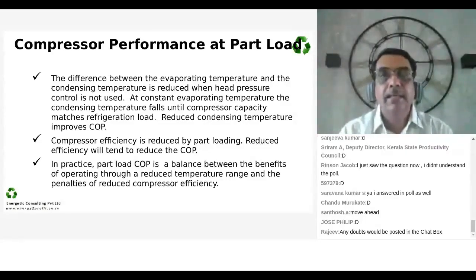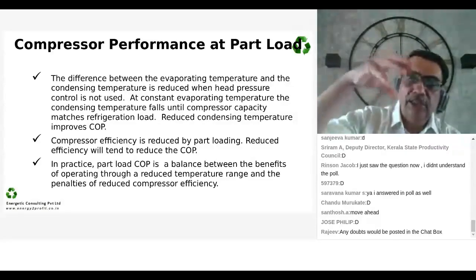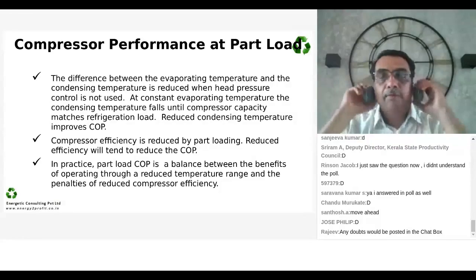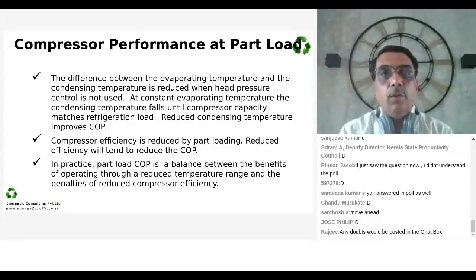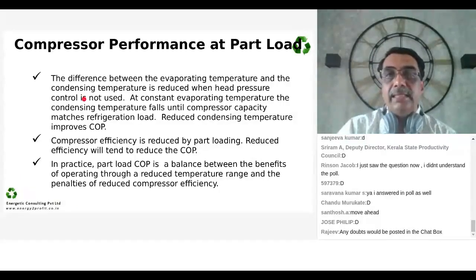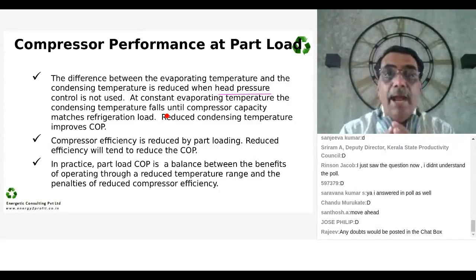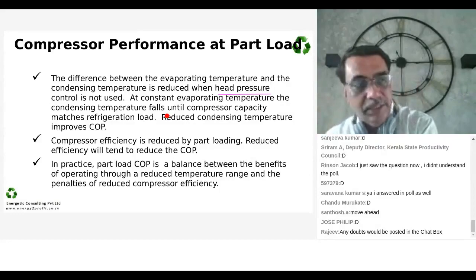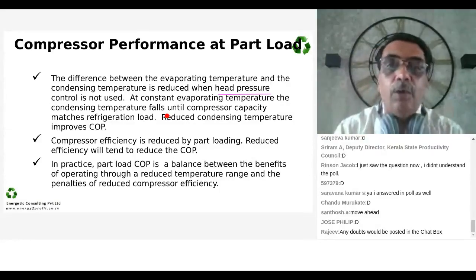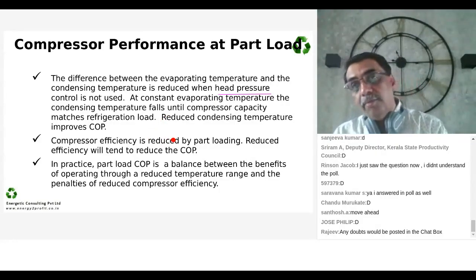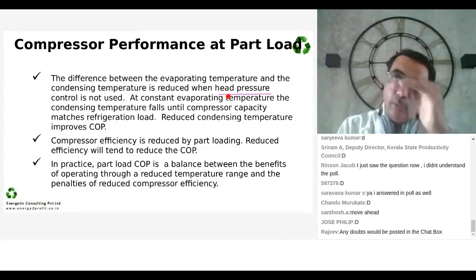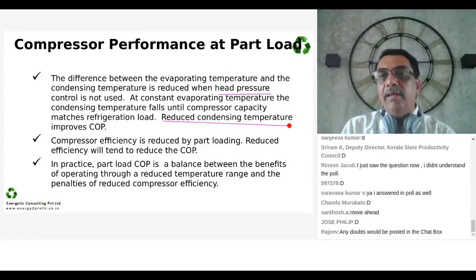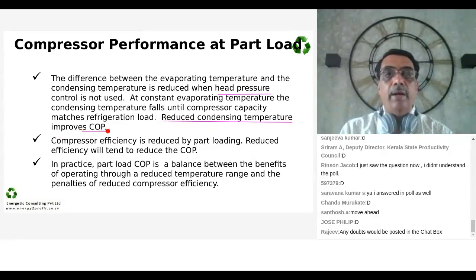Now what happens is, in such a condition, the suction pressure starts going low, which means that the evaporator temperature and pressure are going low. What is done in such a case? There is a head pressure control. What is a head pressure control? It keeps the evaporating temperature constant and allows the condenser temperature to float, which means it is actually condensing at a higher temperature, making the system more inefficient and derating the compressor. Similarly, when the load increases, it allows the head pressure to drop, which means it relatively controls the condensing temperature lower to give a better COP.